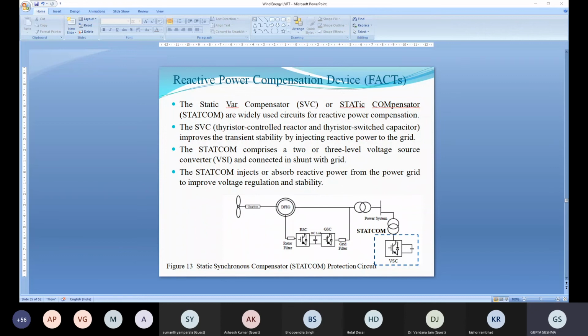SVC, static var compensators, are not used because they cannot provide harmonic compensation, the cost is more, and the space requirement is more. So nowadays StatCom is used in shunt with the power grid to maintain the voltage as well as stability.